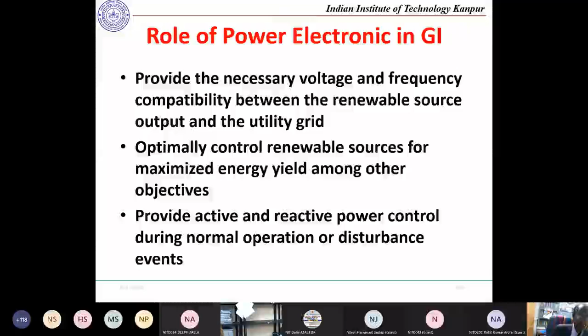Power electronics provides the necessary voltage and frequency compatibility between the renewable energy sources output and the utility grid. It optimally controls the renewable energy sources for maximum energy yield among other objectives, and provides active and reactive control during normal operation and disturbance events. These power electronics can be controlled very efficiently, they are very fast controllers, and that's why they are used in the system.